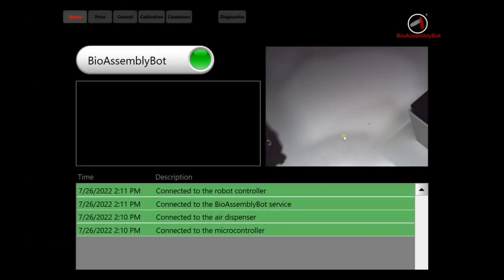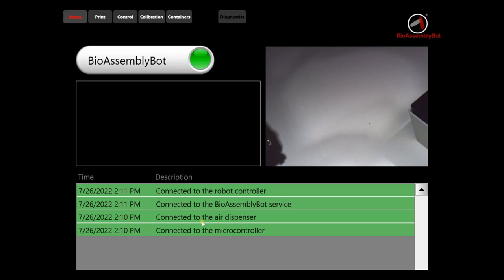The human machine interface, also known as HMI, has several menus and options to control the bioprinter. Today, I will be going over a few commonly used menus and options. On the status menu, we can see the status of the printer and its connectivity. The green light indicates the printer is online and is ready for printing. If this light is in orange or red color, there are connectivity issues and please contact the lab manager for troubleshooting.